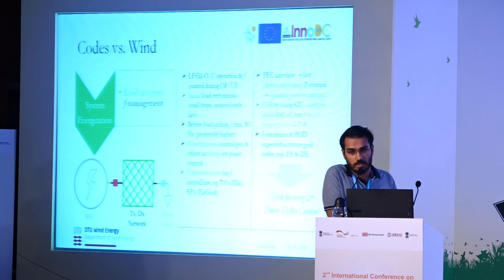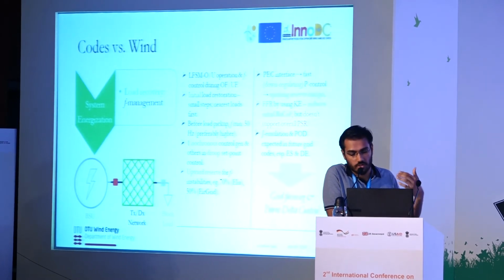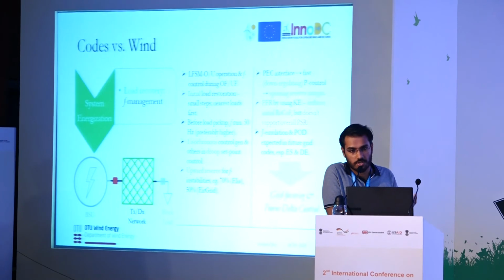Wind turbines, again, because of their power electronics control, can provide very fast ramp up of real power. But the reserve exists more in the down-regulating zone. However, with energy storage, this can maybe even be more beneficial. Fast frequency response by using kinetic energy of the rotating machine can provide some sort of a stabilization to the initial drop of frequency. However, this is not really power system restoration, but some inertia emulation and power oscillation damping, which is expected again in the future grid codes of Spain and Germany, are quite promising features.